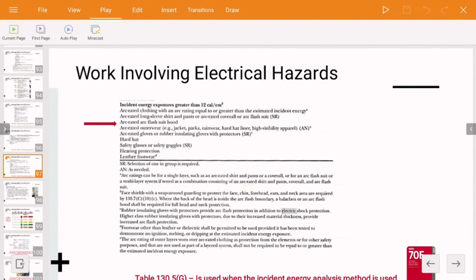So the analysis method is a totally different table. In fact, the analysis method says that if you're going to be exposed to incident energy levels of 12 calories or greater, you have to wear the arc flash hood, okay? Or the astronaut hood, like one of these. So it's a different method.